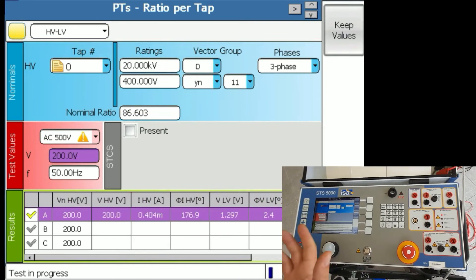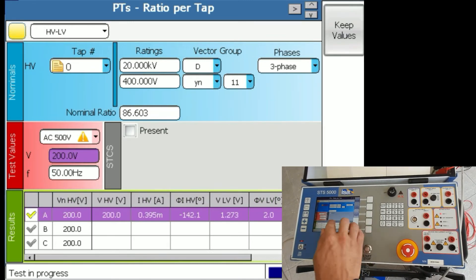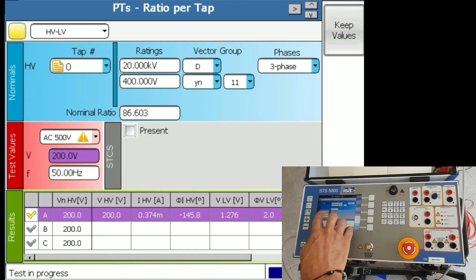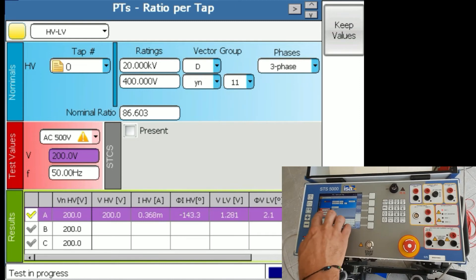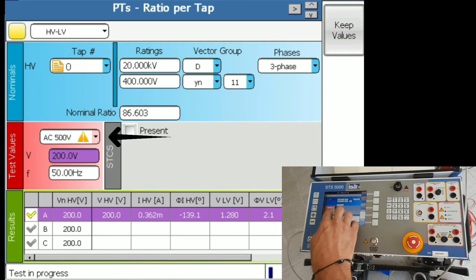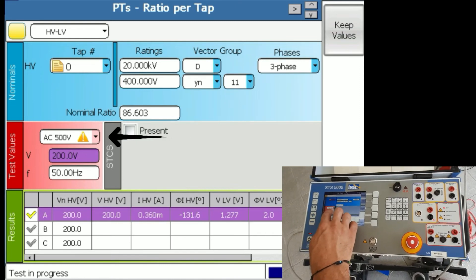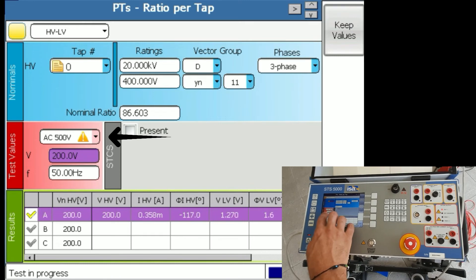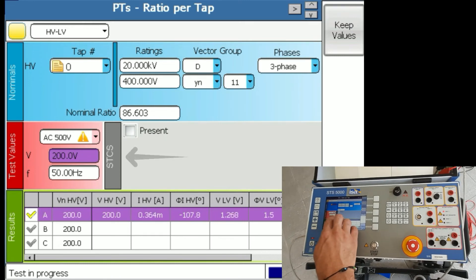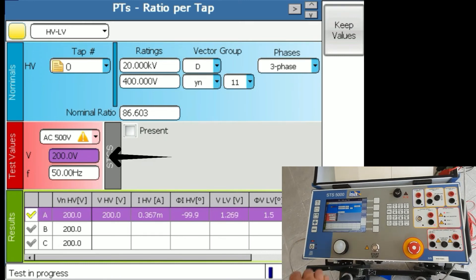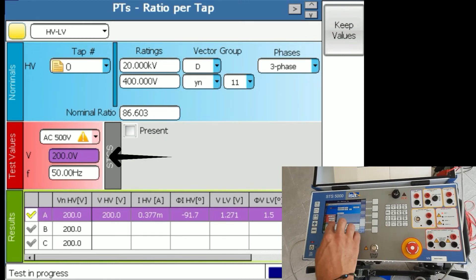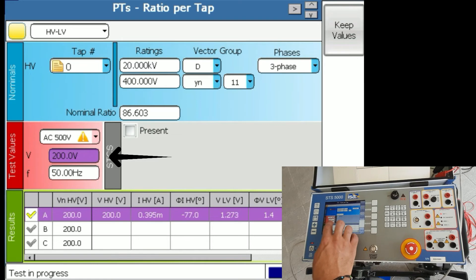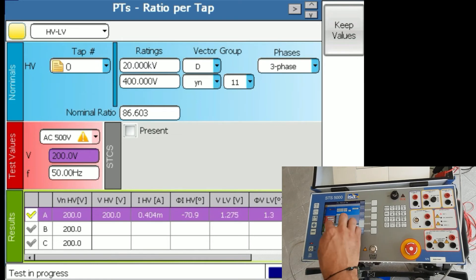And we also need to say, usually I don't touch this, but which output would you use? So I will use the AC 500 volt which is the 2kV output, and I will effectively generate 200 volts on the primary side with 50 hertz. So this is the signal I will be using.